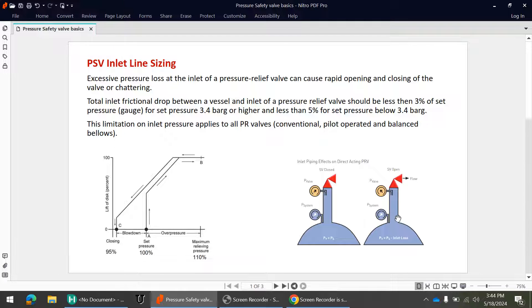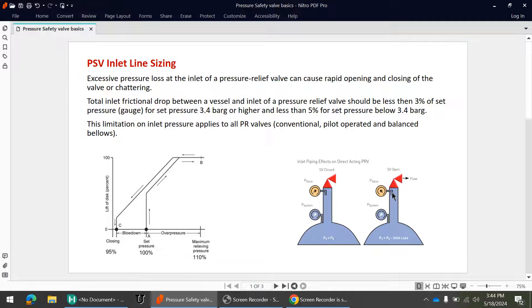In the second diagram, as soon as the PSV opens, flow starts and the pressure at the inlet of the PSV drops. The pressure at the PSV inlet is the system pressure minus the inlet line loss. The blowdown is the difference between the set pressure and the closing (reseat) pressure. If the PSV inlet pressure falls below the reseat pressure, the PSV will suddenly close.